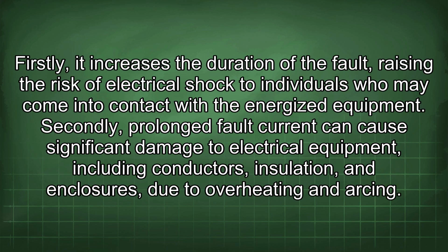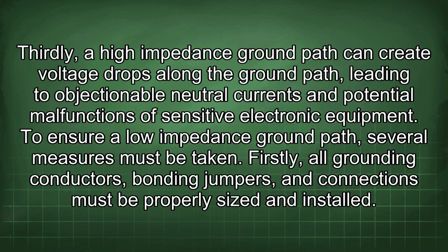Firstly, it increases the duration of the fault, raising the risk of electrical shock to individuals who may come into contact with the energized equipment. Secondly, prolonged fault current can cause significant damage to electrical equipment, including conductors, insulation, and enclosures, due to overheating and arcing. Thirdly, a high-impedance ground path can create voltage drops along the ground path, leading to objectionable neutral currents and potential malfunctions of sensitive electronic equipment.